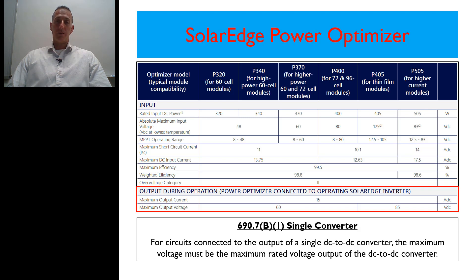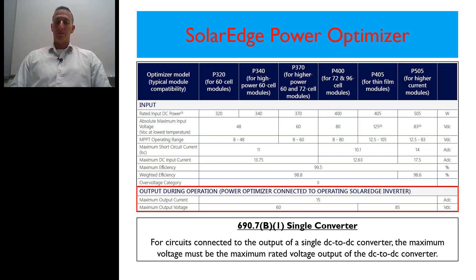Let's get started. In 690.7b1 of the 2017 National Electrical Code, it talks specifically and provides requirements for a single converter. It states that for circuits connected to the output of a single DC to DC converter, the maximum voltage must be the maximum rated voltage output of the DC to DC converter.